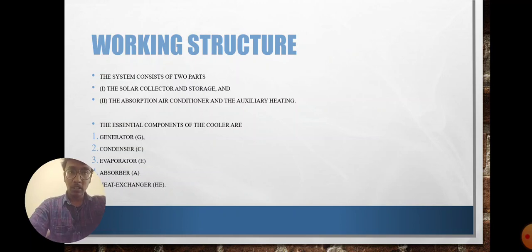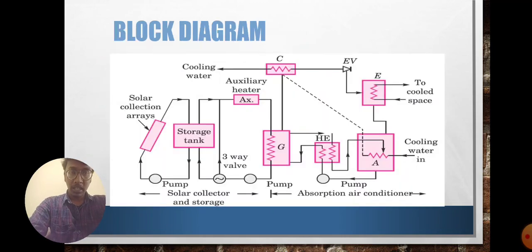And the essential components of the cooler are: first, the generator; second, the condenser; third, the evaporator; fourth, the absorber; and fifth, the heat exchanger. These are the essential components of the cooler. And the block diagram is given, you can go through that. And you can see there is a pump and three-way valve, storage tank, solar collection arrays. In the solar collection arrays the solar energy is stored, and there are the cooling water and cooling space, cooling water inlet, and pump. These are the components used in the solar space cooling of buildings.